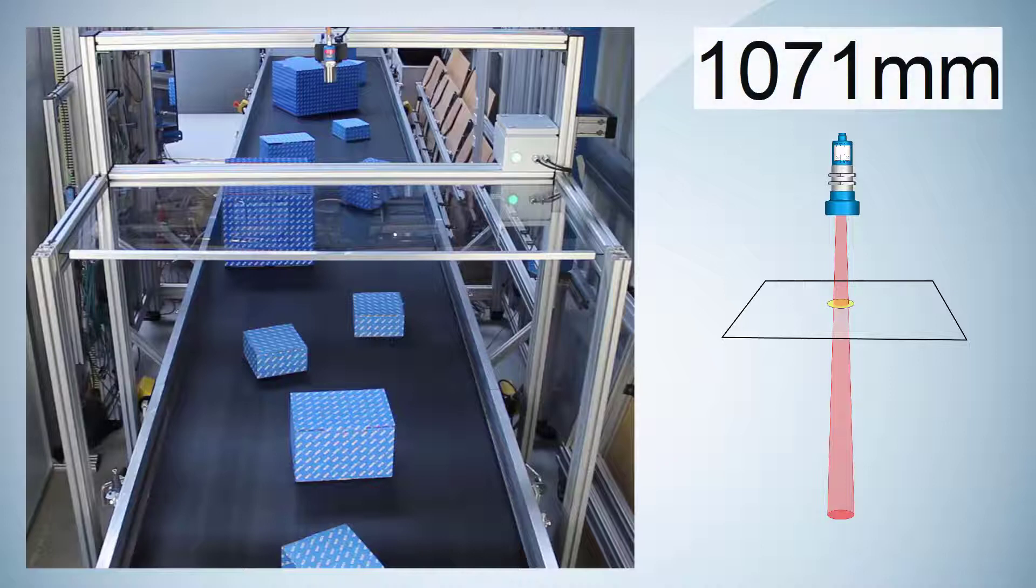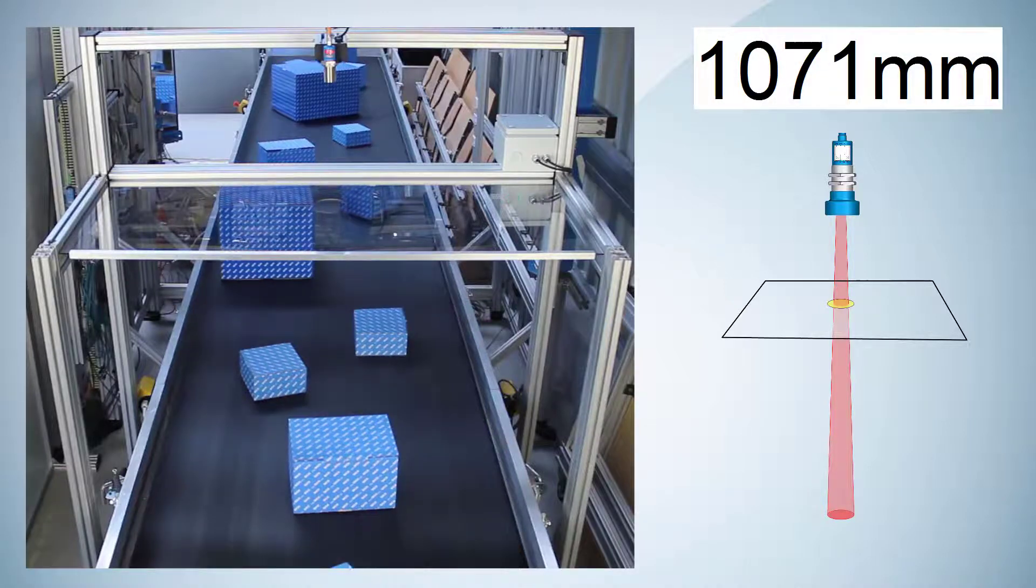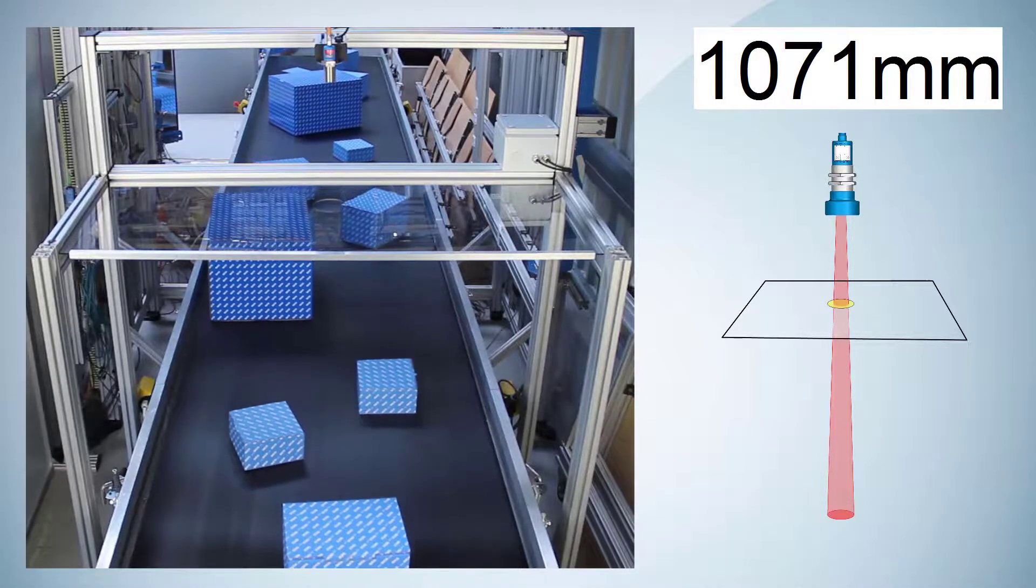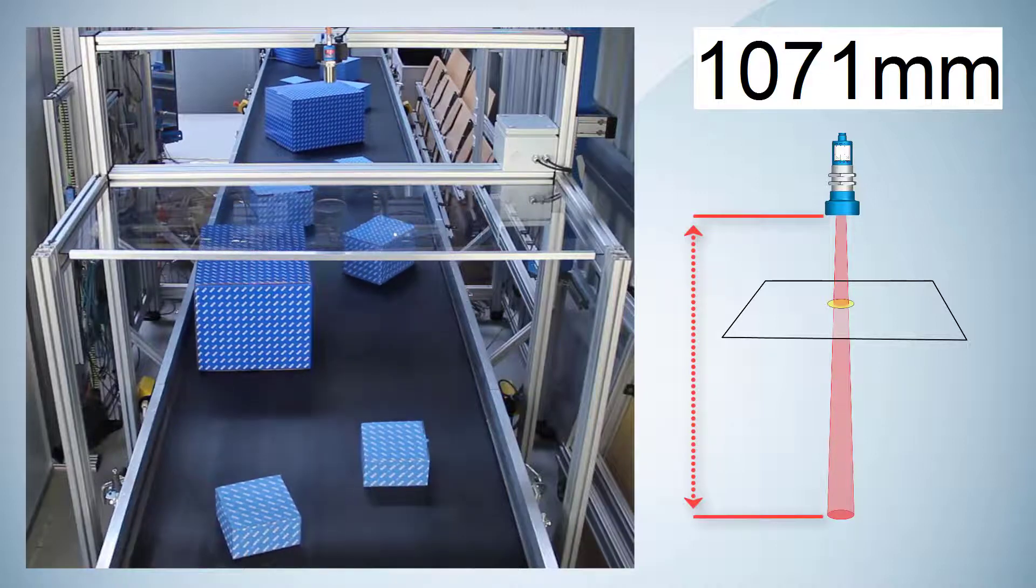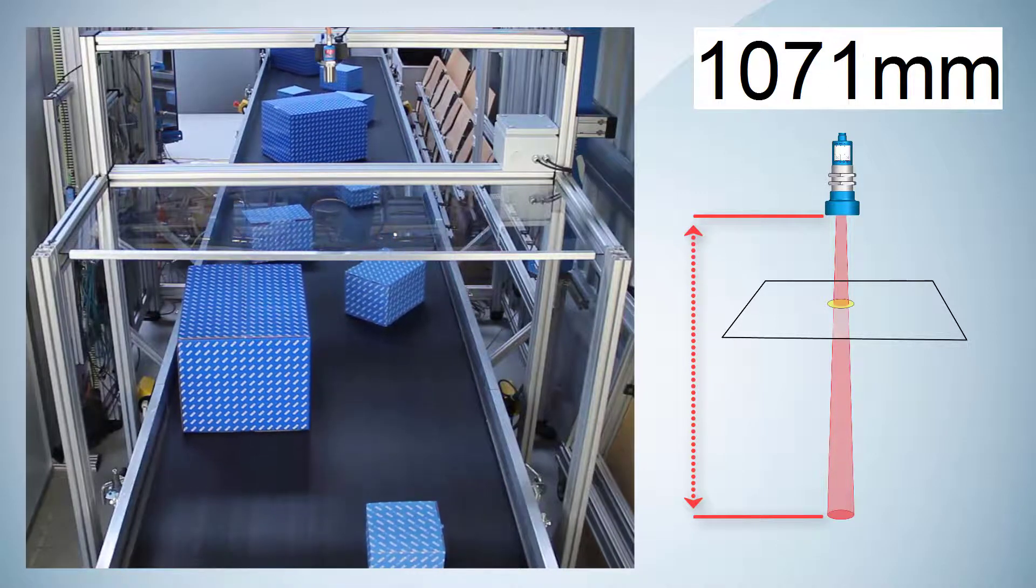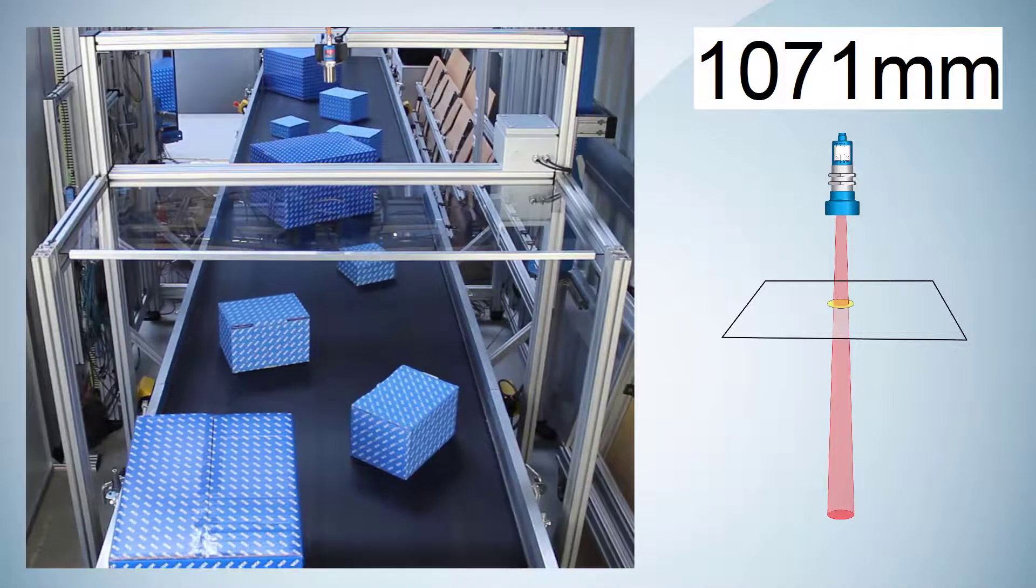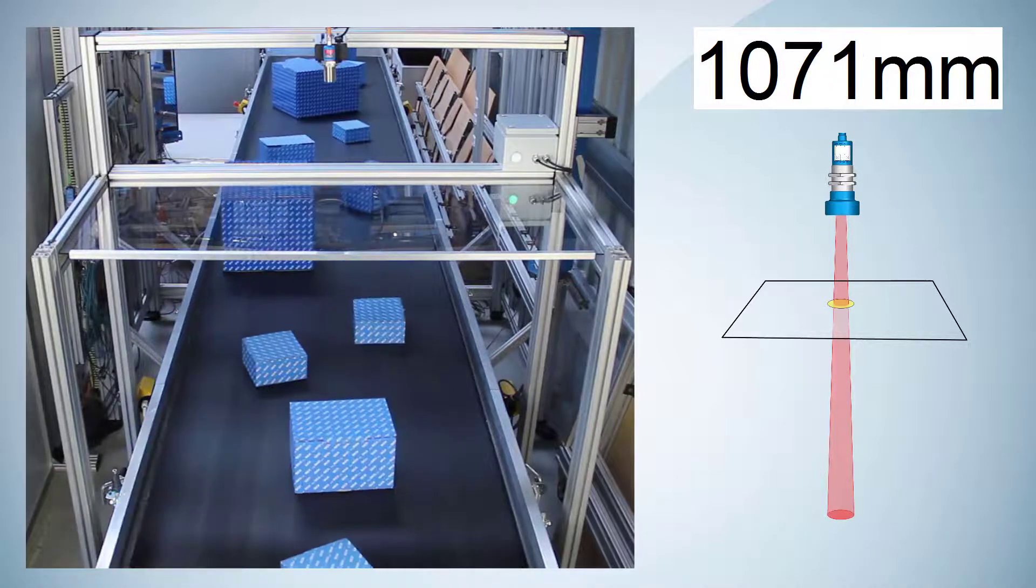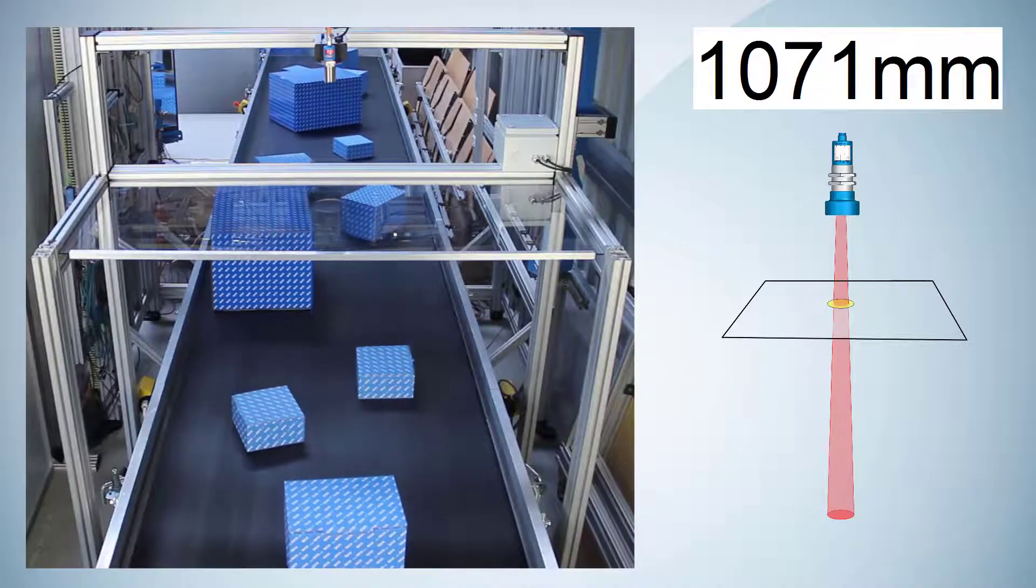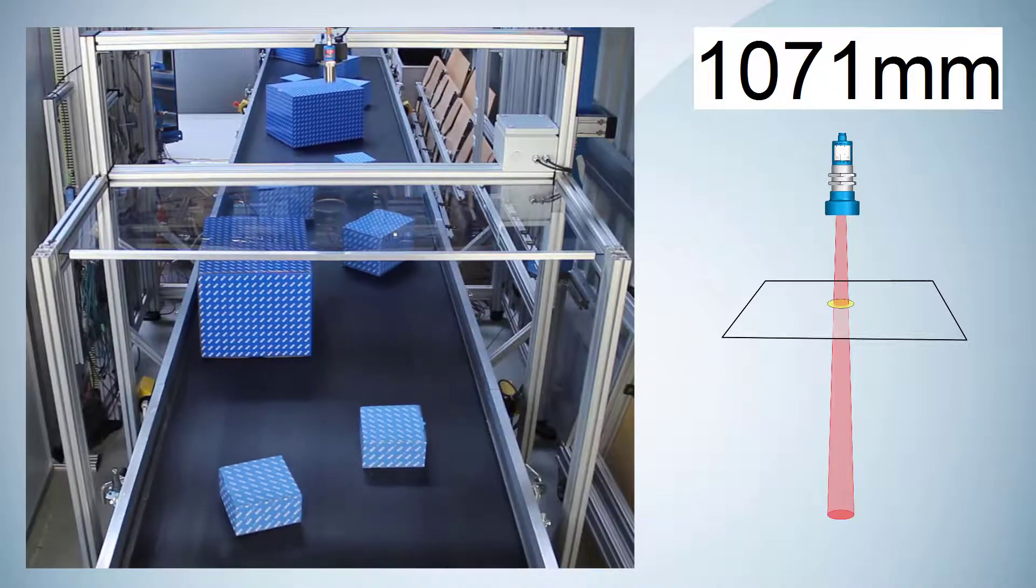The measured value now shows 1071 millimeters, which is the distance between the sensor and the conveyor belt. This means that the sound cone is narrow enough to measure through the hole in the acrylic glass. But now the sensor only detects and measures the distances to the objects placed directly under the sensor head.